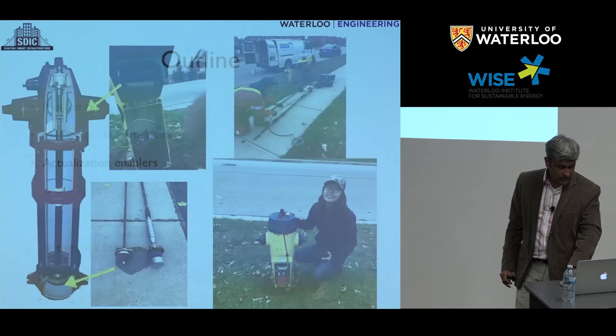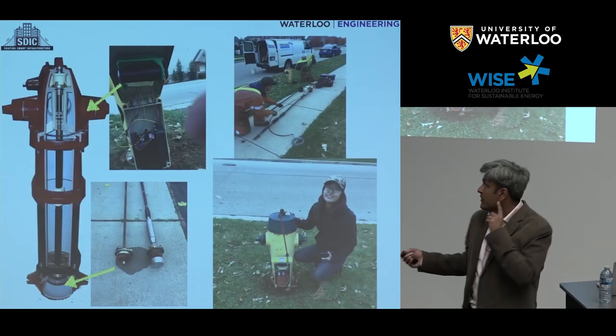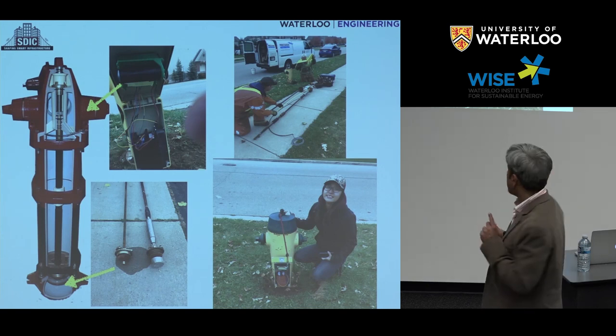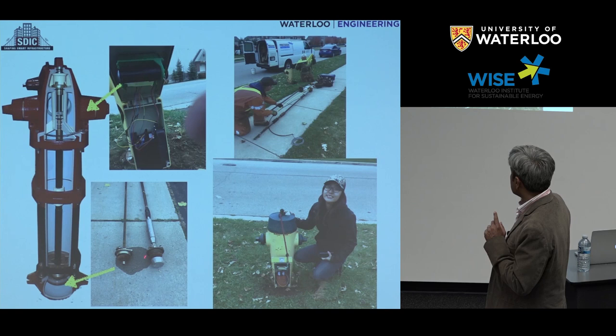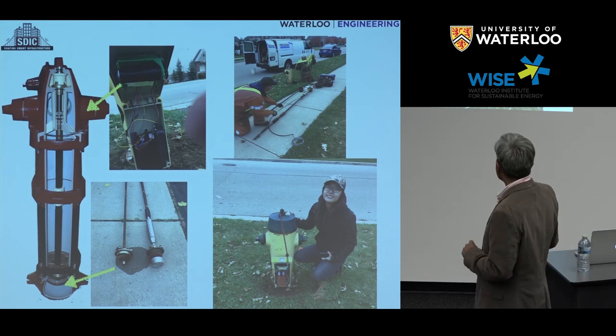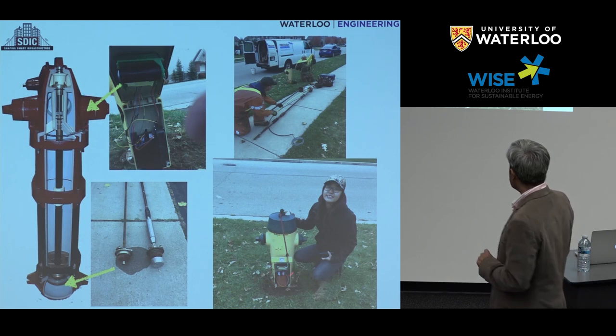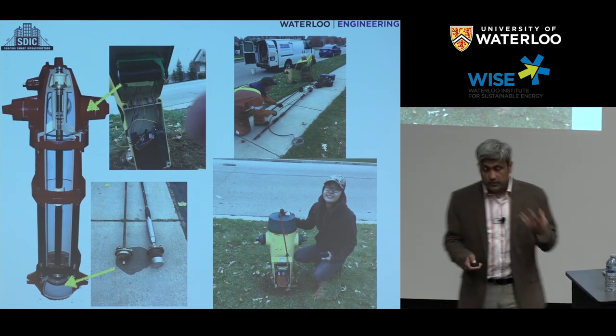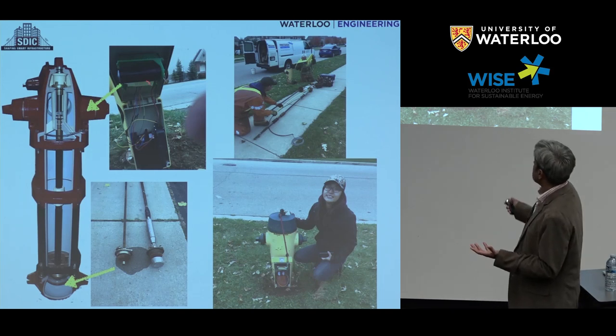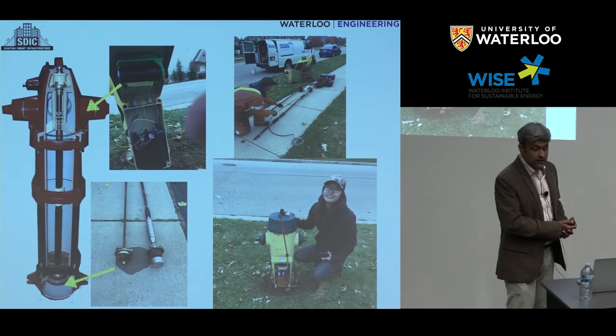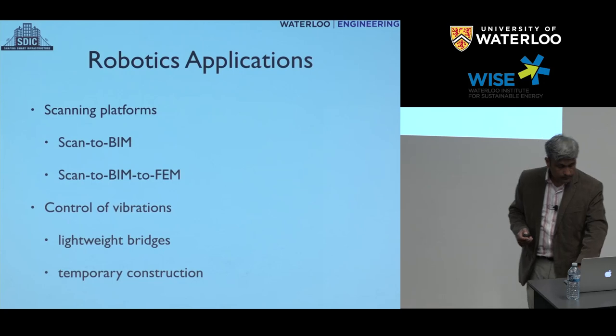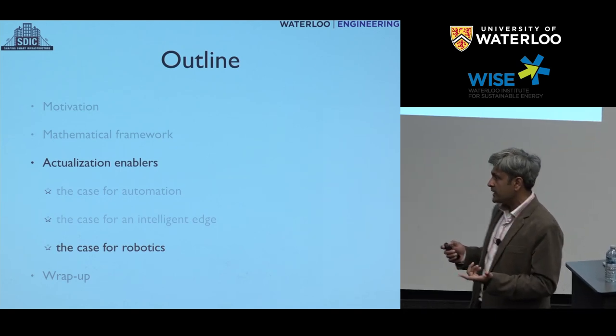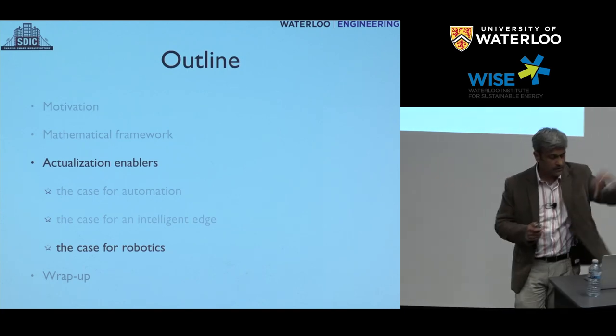Some field tests we recently concluded: this is in Guelph. We put in our first hydrant in November. The backhaul has a power source, radio antenna, and all the microcontroller battery units are sitting on the backhaul. The sensor module goes right underneath into the hydrant stem. There were several hardware issues found in November — we just went back last week with our new hardware prototype which is working well. We are going into the city of Markham and city of Toronto this year, with lots of field trials scheduled to understand how all this data can be utilized.